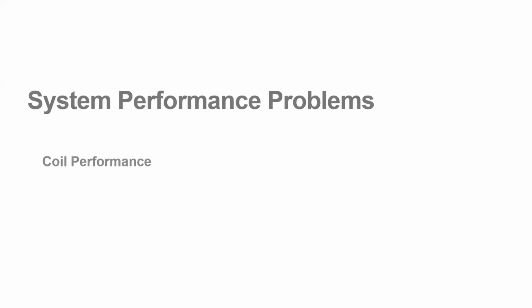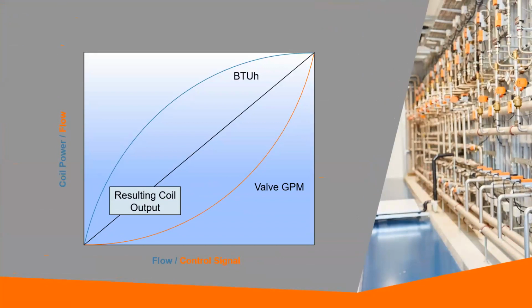Let's look at coil performance now. So remember this graph from earlier, we discussed how the coil curve has a convex shape and starts to flatten out at high flow rates. But what we didn't add, and what we're going to add here now, is our delta T curve as well. You will notice that this has the opposite shape of the coil curve, but for the same reason. Those slow molecules of water that make the curve steep at low flows go into the coil very cool in a chilled water application and come out lukewarm after being in the coil for a long time. This produces a high delta T. By the same logic, faster water will produce a lower delta T. So flow and delta T are inversely proportional.